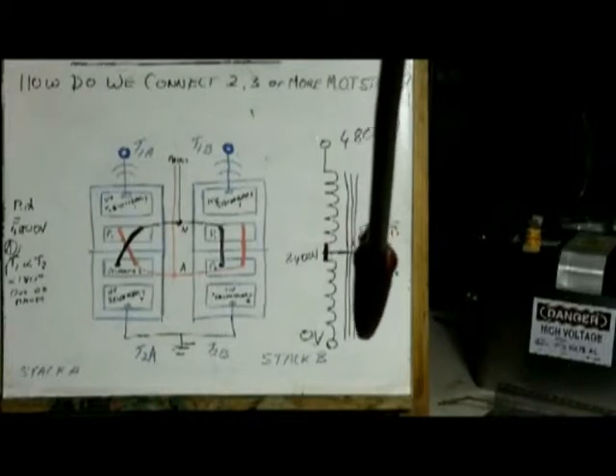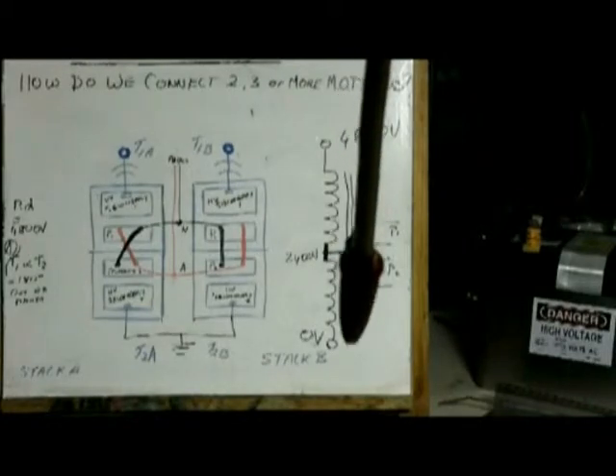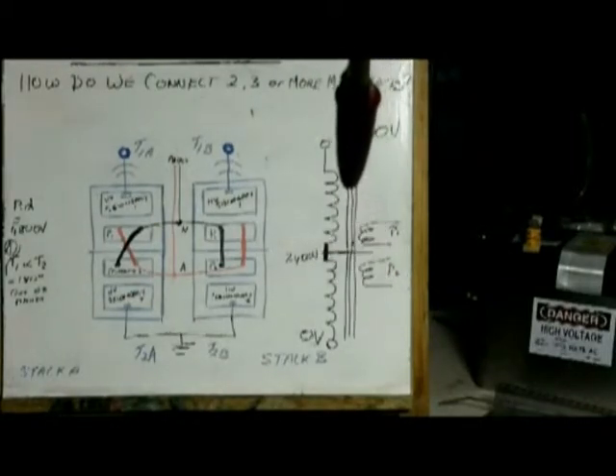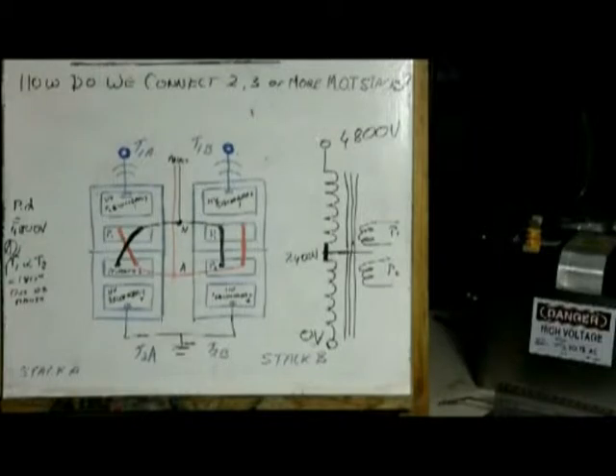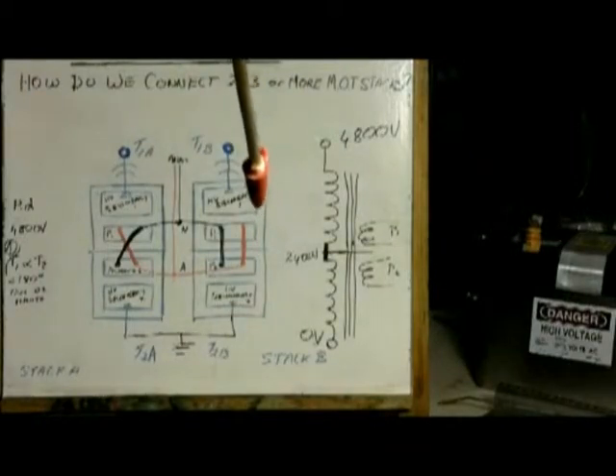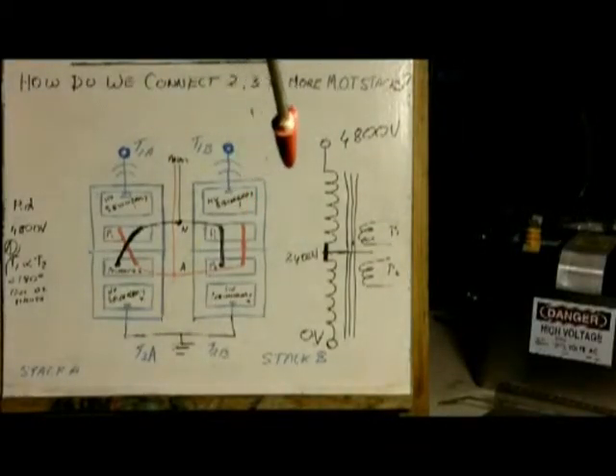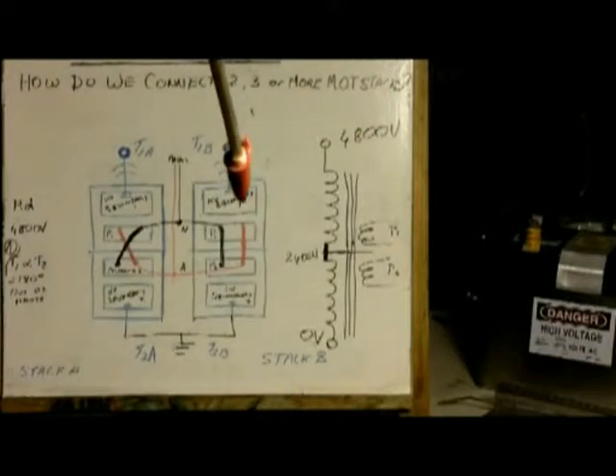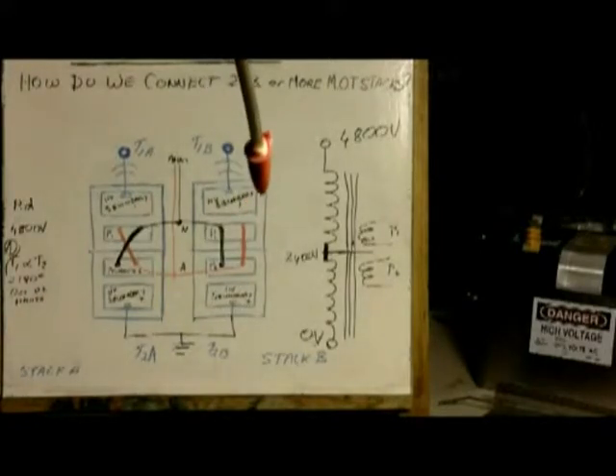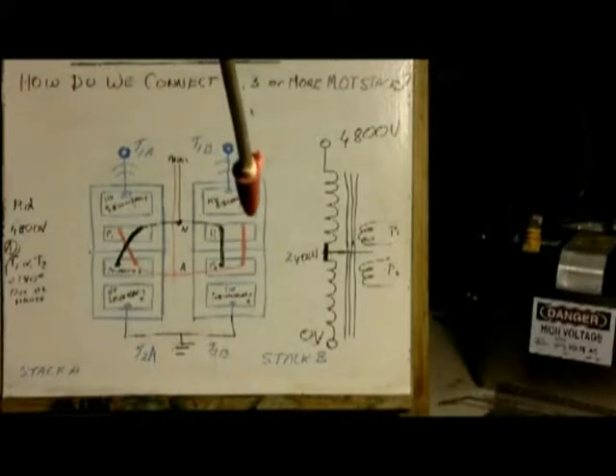The winding runs very, very close to the core, so you can't actually disconnect it unless you're planning to dismantle it, so it's probably best left alone. It's not a bad arrangement. See, by having a potential of 2,400 volts on the core, and if the voltage is 4,800 volts or thereabouts, you only have a potential difference of 2,400 volts between the winding and the core, which, as you know, it's designed for.